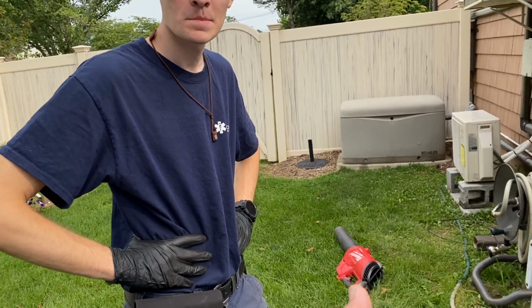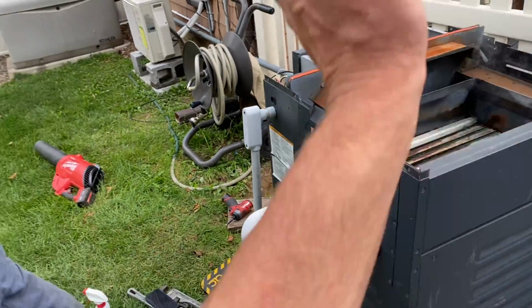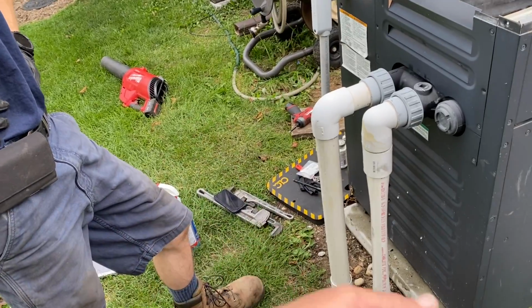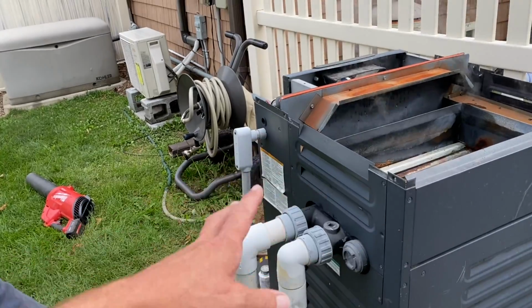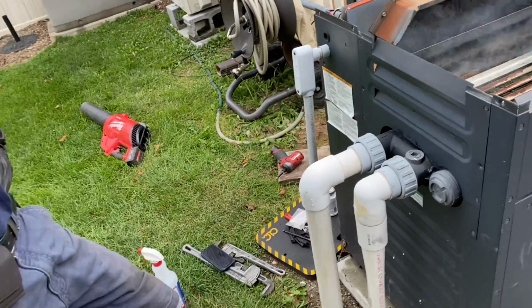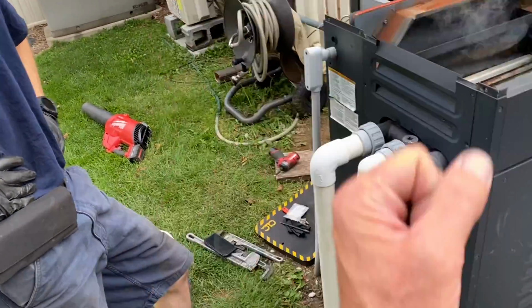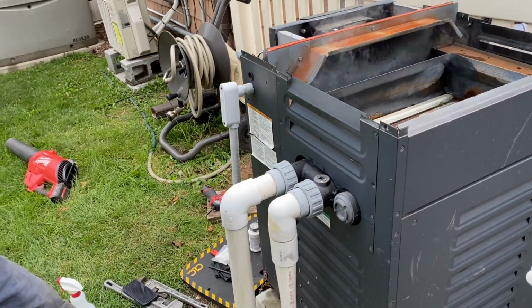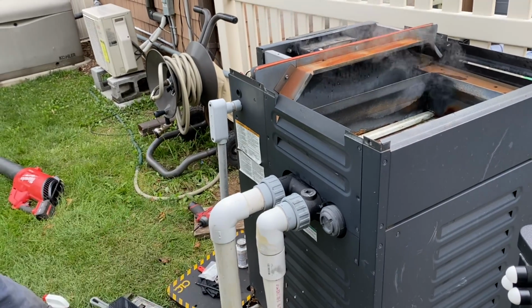Let's say you have a carbonized boiler, you have that soot, that carbon buildup all in the cast iron heat exchanger, in between each section, right? I like to take out the burners below, disconnect the gas, of course, take out the burner tray, disassemble the top of it, take the top cover off, take the hood that's inside here off, and then with the soot vac and brushes, have you done that? Yeah, you probably did that at your last company. You take brushes and you vacuum it down, and you suck all the carbon or the soot out of the boiler. Never be 100%, but some guys say, just use water and it'll work too.